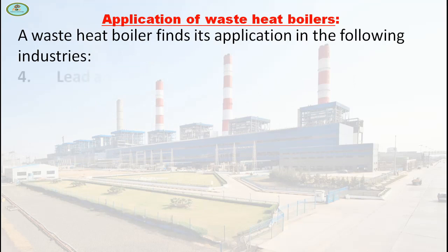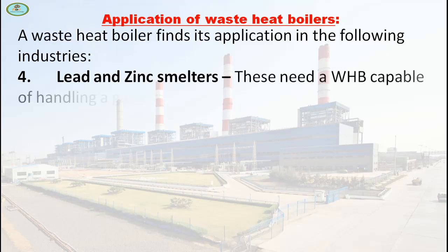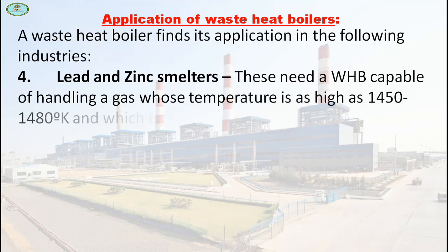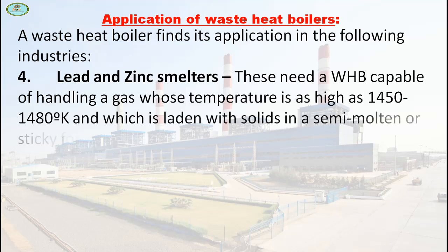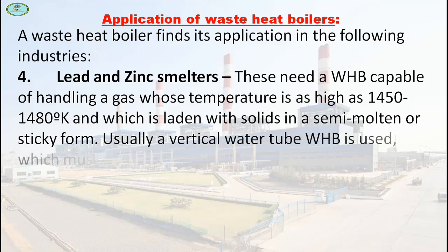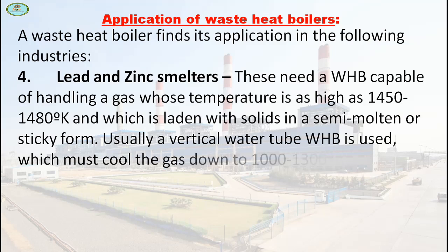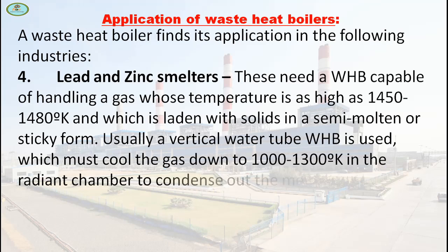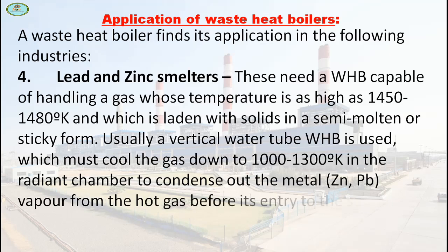Next is lead and zinc smelters. These need a WHB capable of handling gas whose temperature is as high as 1450 to 1480 Kelvin, which is laden with solids in a semi-molten or sticky form. Usually a vertical water tube WHB is used, which must cool the gas down to 1000 to 1300 Kelvin in the radiant chamber to condense out the metal vapor from the hot gas before it enters the superheater and convection shaft.